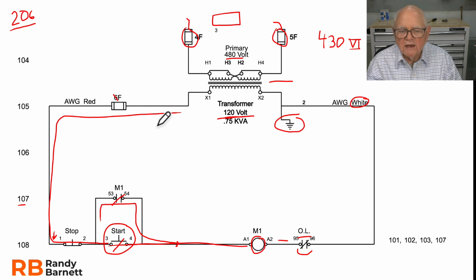By the way, while I'm talking about it, as far as the raceways, can I put the wiring for this control circuit inside the same raceway conduit as that main power circuit? And the answer is yes. It's found in Article 206. It tells me that I can, as long as I meet the insulation requirements on the conductors. And the insulation requirements for this control wiring have to be no less than 600 volts. So I shouldn't have any trouble with that, right? And also they're functionally associated, obviously, the control circuit and the main power circuit for the motor. So yeah, I end up being able to put them inside the same raceway. But let's get back to sizing these conductors.